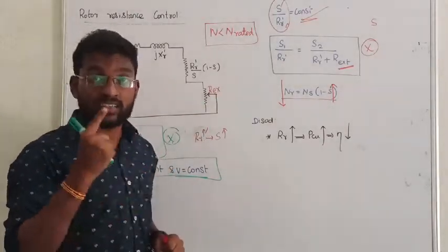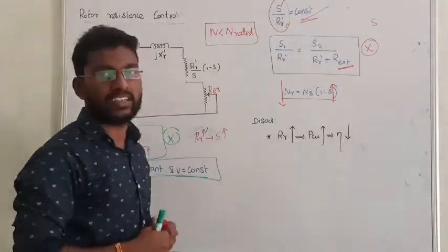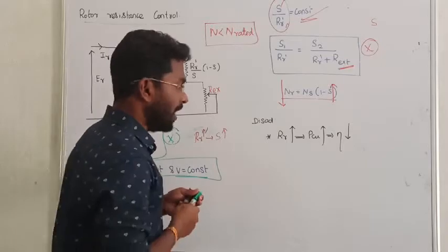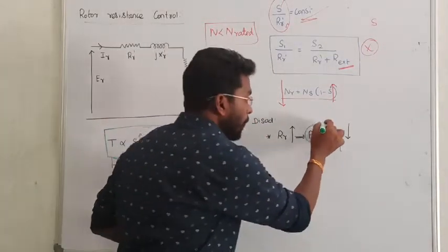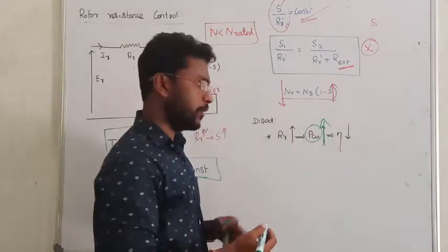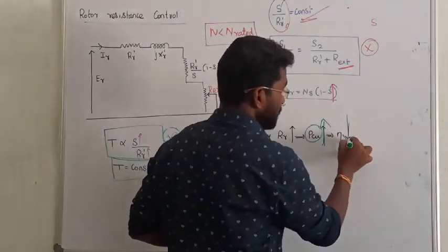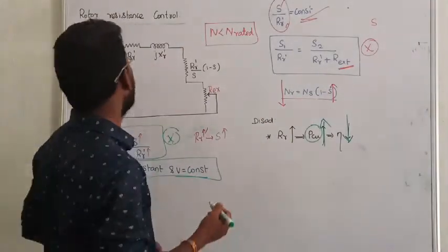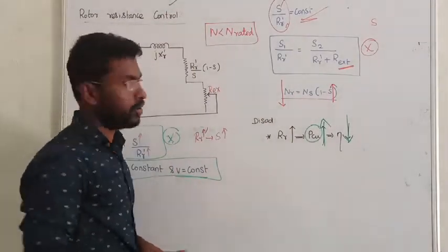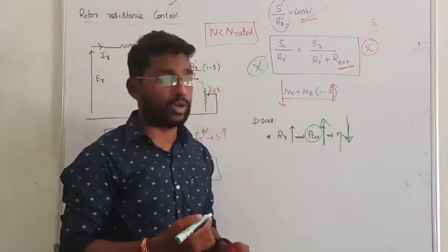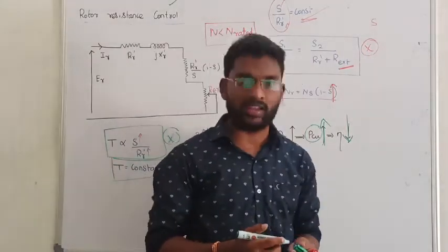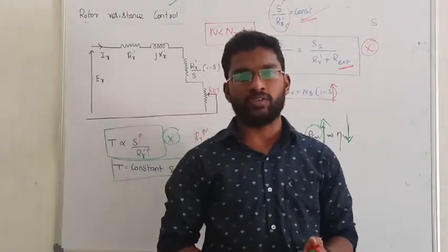What is the disadvantage? Additional resistance - there will be a loss, that is copper loss. In our induction motor copper loss will be increased. Loss is increased, so the motor efficiency is getting reduced. That is the drawback of rotor resistance control. So I hope you all understand. If you have any doubts you can ask in the comment section. Thanks for watching our videos, thank you all.